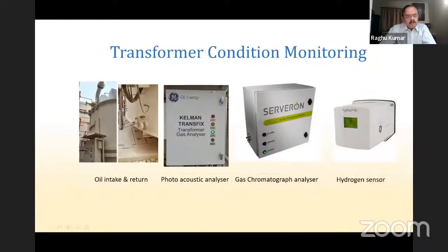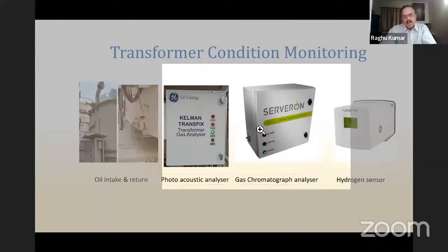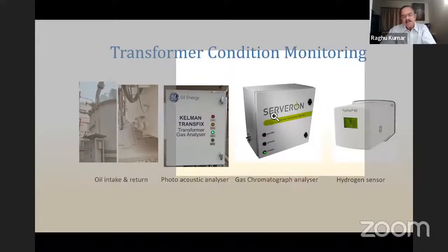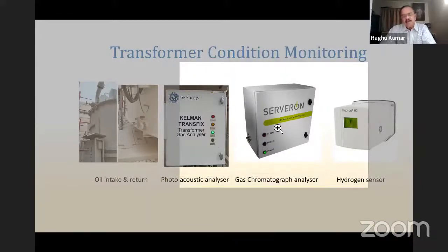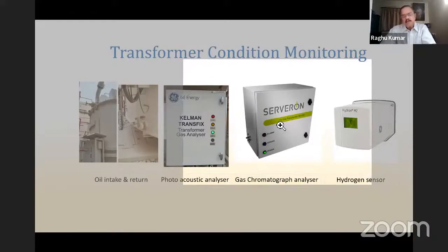These are some of the equipments which are used for online monitoring. This Kelman Transfix is an equipment which works on the photoacoustic principle. And Serveron is an equipment which works on gas chromatograph. Gas chromatograph has a maintenance issue in the sense that it needs a carrier gas. Helium is the carrier gas here, and this helium needs to be replaced every 2 to 3 years. And once you replace it, calibration is required.